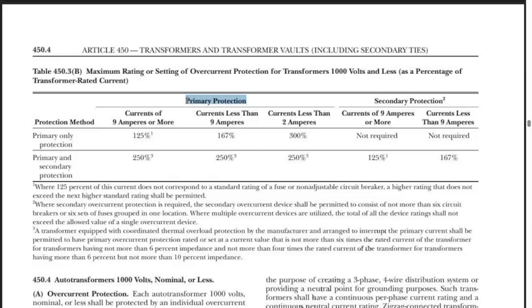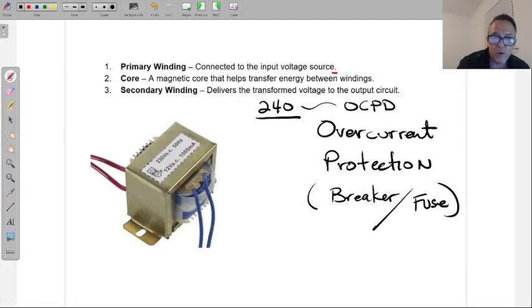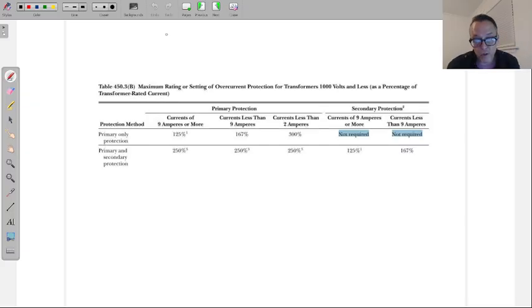Now, the primary side, and this is what I wanted you to focus on. Notice the size of the amperages running through these transformers. They are very small. Amperage less than 2 amps. For my students who did motor control, your control circuit transformers have less than 2 amps on them. So sometimes there's small transformers that are operating in systems that are running less than 2 amps through the conductors, through the wires. Very, very little amperage, because they're more so concerned about the voltage.